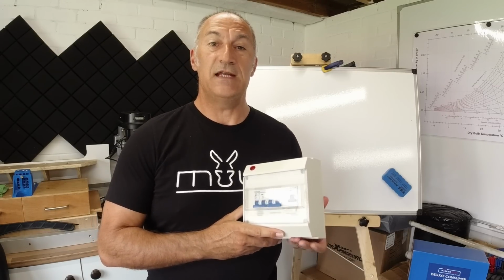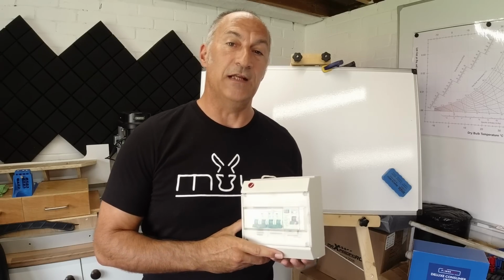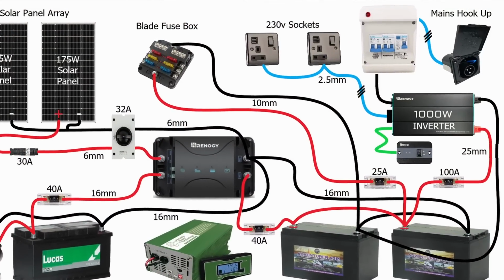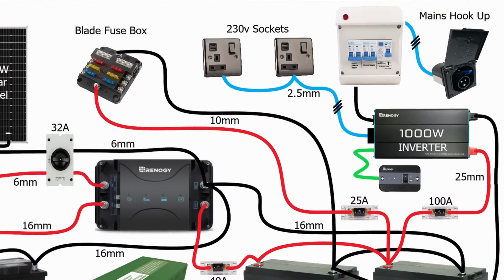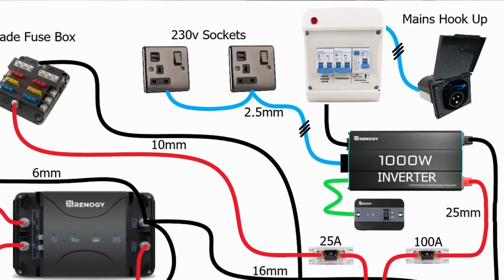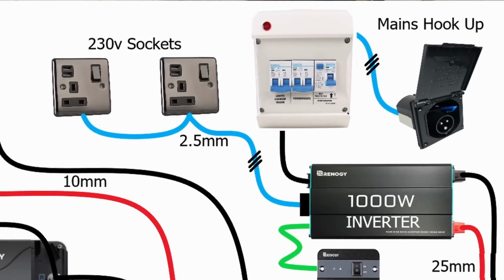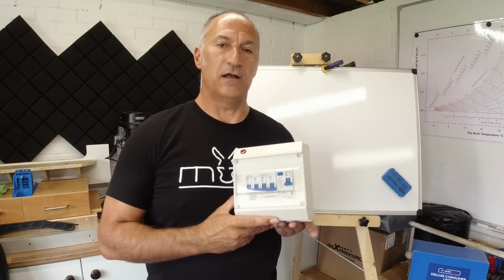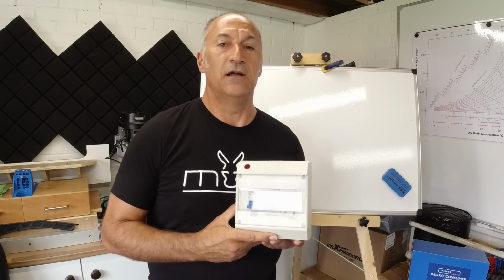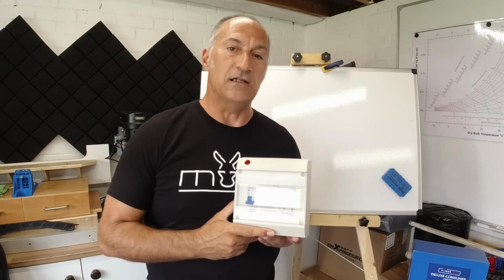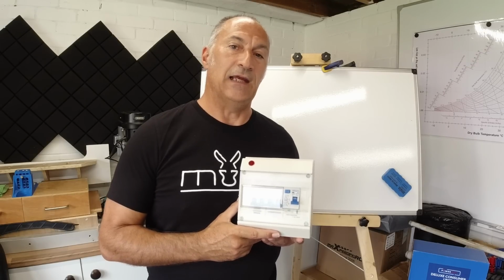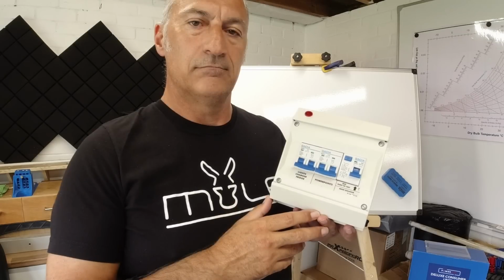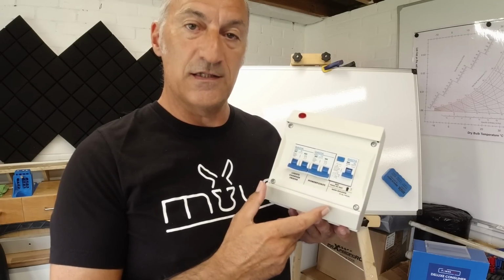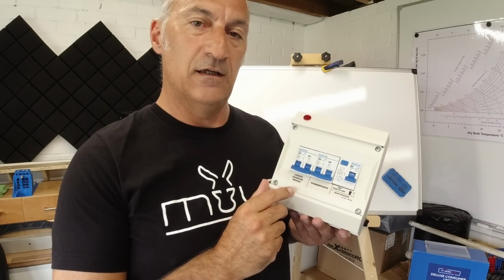As many of you pointed out on my previous wiring diagram video, I should have shown a consumer unit directly connected to the hookup connection coming into the van, and you're absolutely right. In order to comply with current British standards, a consumer unit is needed to be installed in our van on that incoming mains supply. Inside the consumer unit there's a couple of different devices.